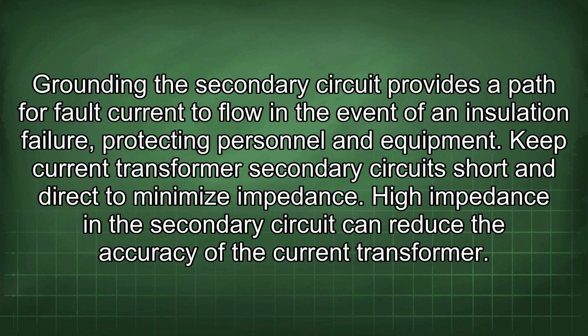Grounding the secondary circuit provides a path for fault current to flow in the event of an insulation failure, protecting personnel and equipment. Keep current transformer secondary circuits short and direct to minimize impedance. High impedance in the secondary circuit can reduce the accuracy of the current transformer.